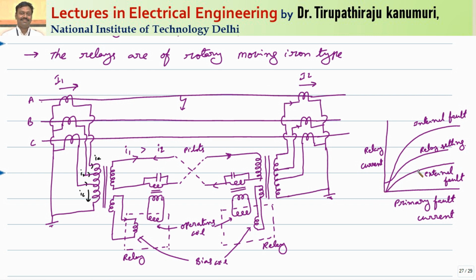For external faults, only the difference in current passes through your relay, because the relay responds to the difference. This difference can increase with the increase in primary current, due to mismatch in the CT characteristics, but the torque produced is very less. Whereas in the case of an internal fault, even though the CT mismatch is there, the difference in the currents is more, so automatically the relay current and the torque produced are more. That's why your relay will operate. We will make the setting in between that, so accordingly your relay will operate.